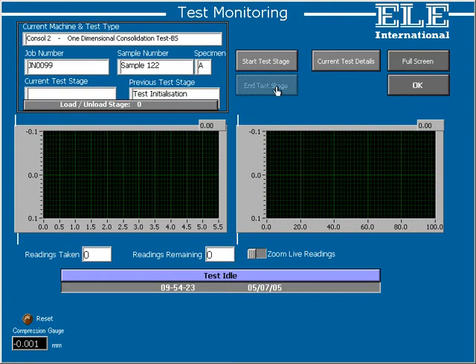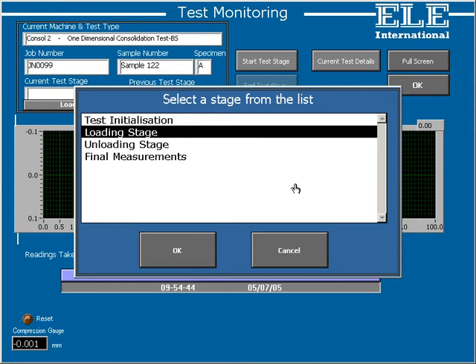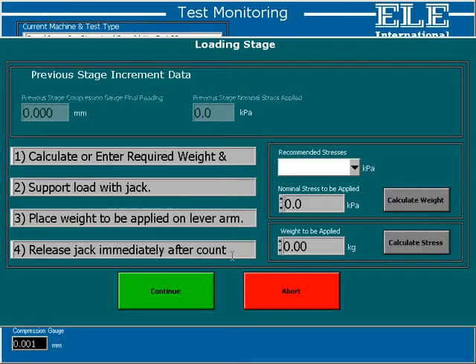At the top right are the control buttons, used for monitoring and controlling the test we're currently looking at. Let's take a look at how we start a loading stage for our oedometer test. Here's a list of the possible stages — select loading stage and OK. As simple as that. The following screens then lead the operator through the process of adding the required weight and starting the test. Down the left hand side is a set of simple instructions for the operator, and this is typical of running any test within DS7.